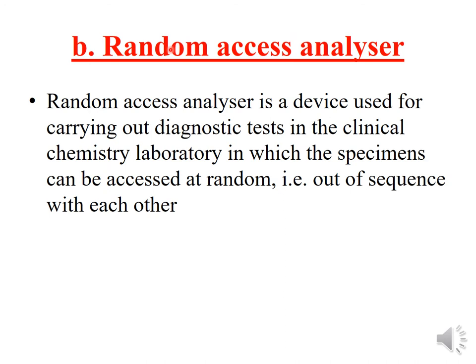The random access analyzer is a device used for carrying out diagnostic tests in clinical chemistry laboratory in which specimens can be accessed at random — that is, out of sequence with each other. If you want to change the sequence for some reason, in a random access analyzer this can be done.